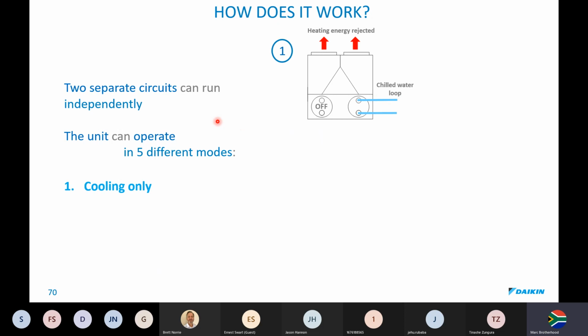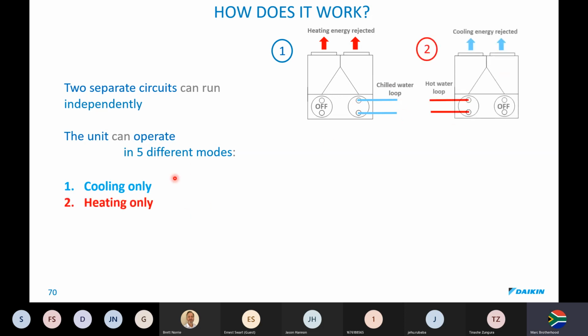So how does it work? We have 2 separate circuits which can run independently. Here you notice this is the one set of heat rejecting coils, which is air cooled, and here we have our 2 shell and tube heat exchangers. The unit can operate in 5 different modes. Let's say we want cooling only, it's going to work like a normal chiller. Heat rejected, warm water in, cold water out. Or we can use it only as a heat pump. We switch off the cooling, it's still going to run. Your condenser is going to become your evaporator, and we're going to generate hot water to the building.